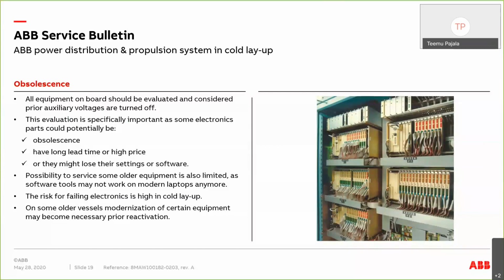But an even more important thing is that when you switch off old electronics, there is a high risk that they don't start up again. Especially if the system has been switched off for a longer period of time, the capacitors tend to dry, and when you switch on power again, they start to blow up. There can be random failures here and there. Capacitors blow up and then you get all kinds of strange behaviors in the system. And that's a general rule for all electronics, not only in the layup condition.